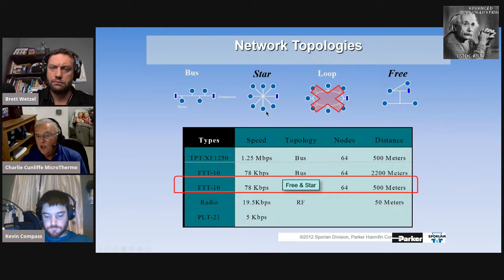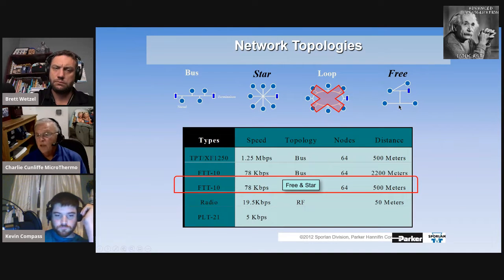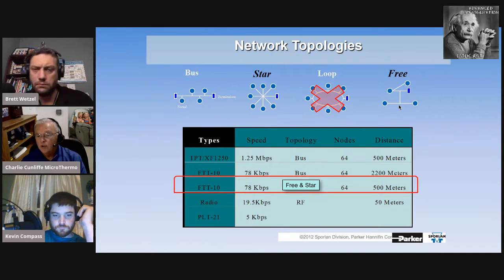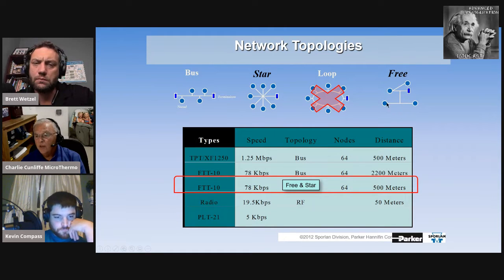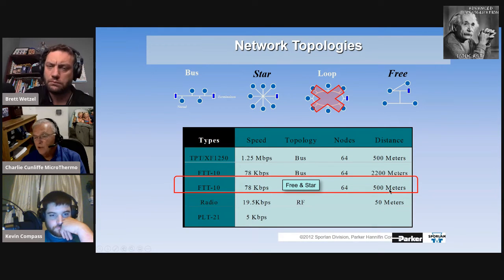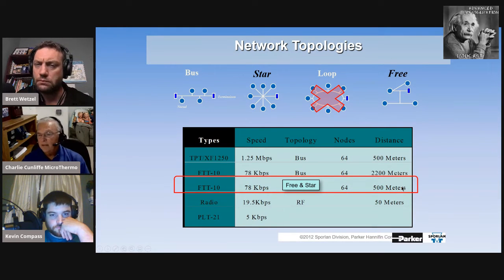For me, that's easy to wrap my head around if I'm going to go to a store and troubleshoot. But with free topology, that's got to be committed to writing someplace, because it's freelance. You can make the network whatever you want, as long as each subsegment can't be more than 64 simple nodes and no more than 500 meters or 1,640 feet.